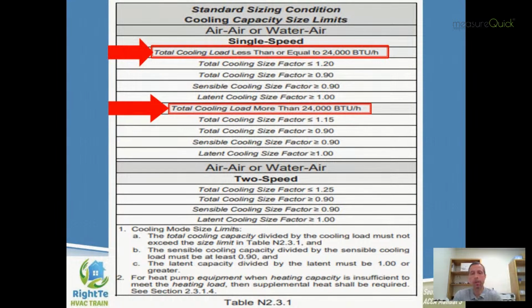So if you look at the top of that chart where it says air to air, air to water, single speed, you'll see that we've broken that up and defined it a little bit better. The red arrow up at the top is pointing out that we now have two different sets of potential sizing limits or criteria there. This is the first part for systems up to 24,000 BTUs per hour. And there we're really talking about the cooling load, not the system capacity, but the cooling load. And then the second red arrow is for homes having a cooling load of more than 24,000. And the reason for that, you'll notice that we expanded the parameters here.